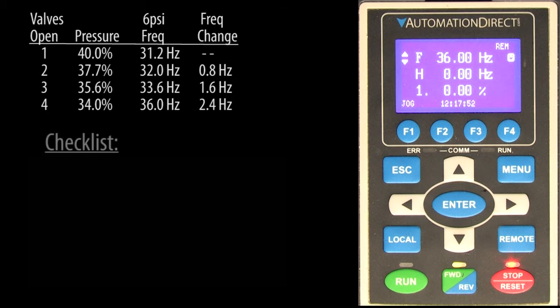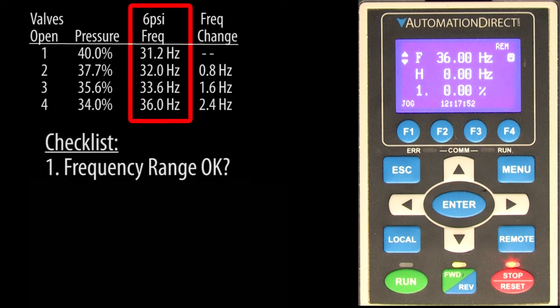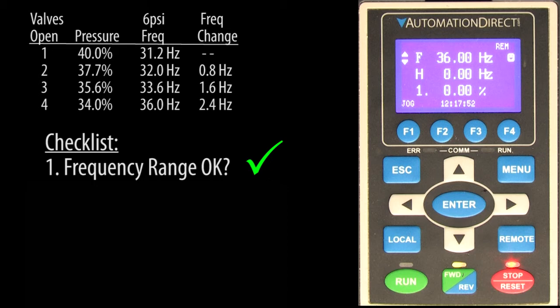Before we implement that, let's check a couple things. First, we see that since we are only using roughly 30 to 40 Hz of the drive's 60 Hz frequency range, we now know the drive has more than enough frequency range to compensate for the pressure drop even when all valves are open. That's really important to know.